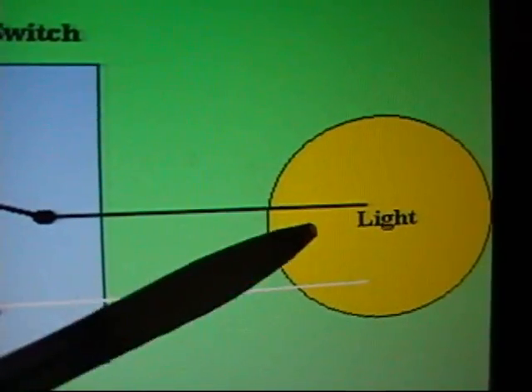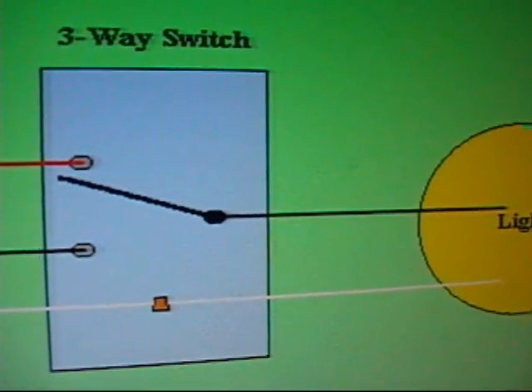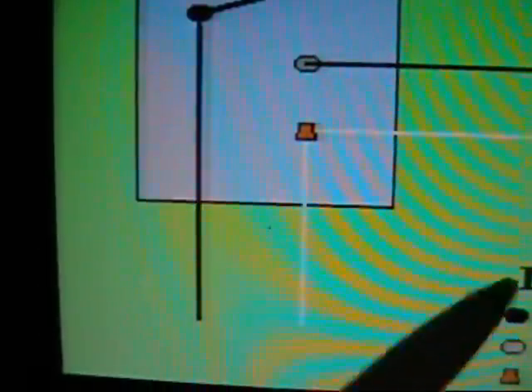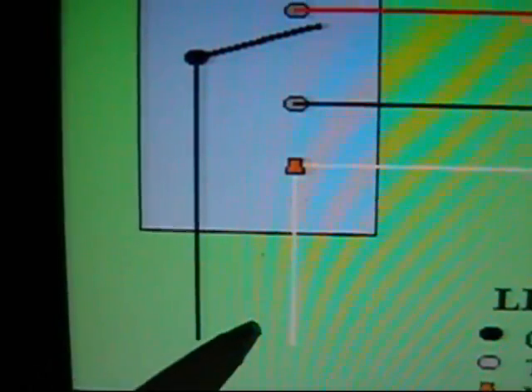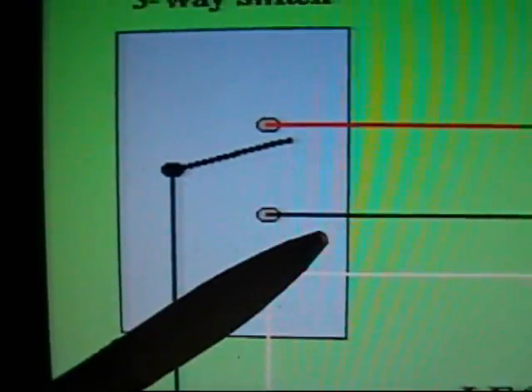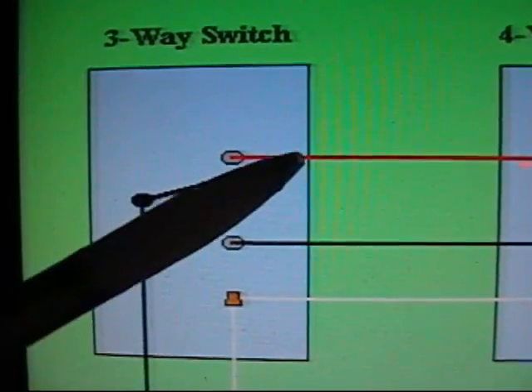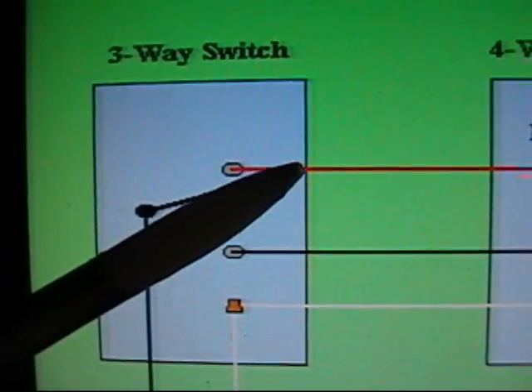Like I say, you could have several lights all controlled. Doesn't have to be one. It could be five, six, or whatever, up to the maximum capacity of the circuit and the switch. Usually use 14-gauge wire for lighting, but you can use 12. Actually, coming out of the panel circuit breaker panel, you're going to have your typical 14-2 with ground. But then coming out of your switch, you're going to have to go to 14-3, which in this case will have a white, it'll have a black, and it'll have a red as well as the bare ground wire.